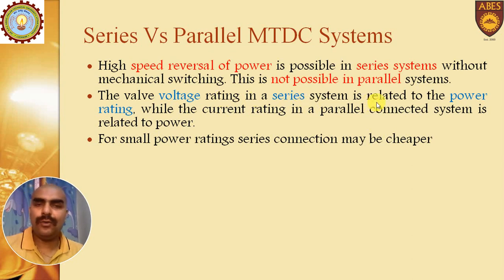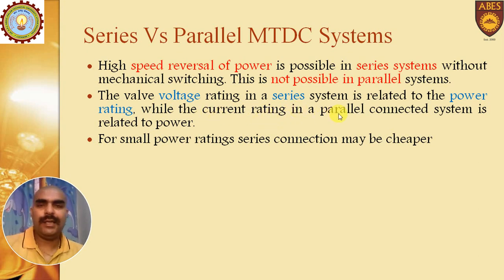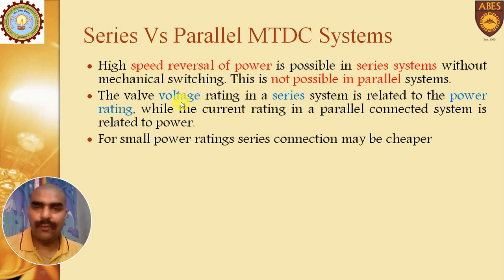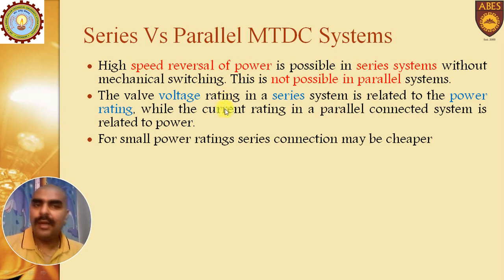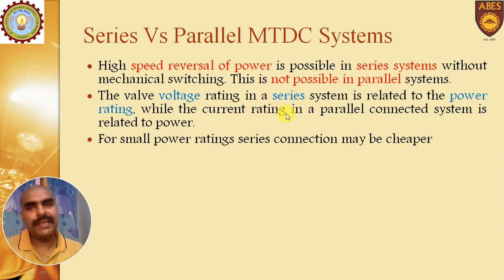Second point: valve voltage rating in series system is related to power rating, while the current rating in parallel connected system is related to power. Series valve voltage rating is related to power, and parallel valve current rating is related to power, because in series current is constant and voltage is variable, and in parallel voltage is constant and current is variable.